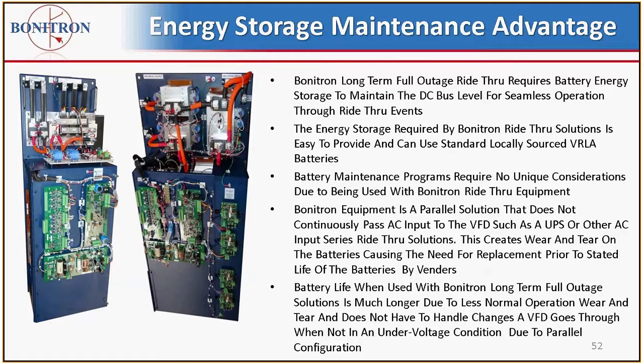Another advantage to Bonitron battery systems is that we have found that our batteries last much longer because they're not in series and there's not a constant AC line voltage being applied to the unit, as with series solutions that have input AC and output AC, such as UPSs or some of the dynamic sag correctors that are out on the market. So in other words, we don't beat up the energy storage, because a UPS is going to activate anytime there's an issue with the AC line. And also, transients or other things can affect the AC solution more so than the Bonitron parallel solution.